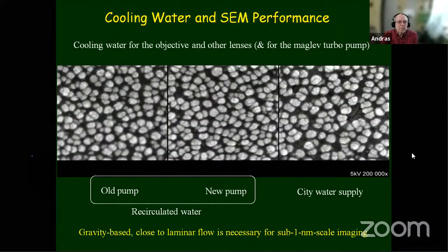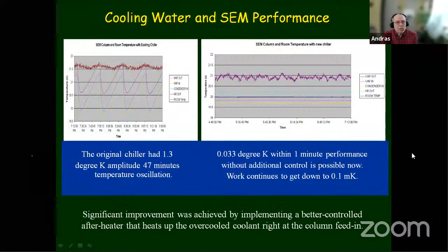Go to the next slide, please. So you can see that we had a chiller which had quite a bit of temperature variation, and we replaced it with another one. What we do on our instrument is we overcool the water, and we have a local little heater that keeps the temperature, because we measure the ingoing and outgoing coolant temperature and get a much better temperature regulation, because of drifts and other problems occurring when you heat up or cool down your electro-optical column components, depending on how your chiller works. Next slide, please.